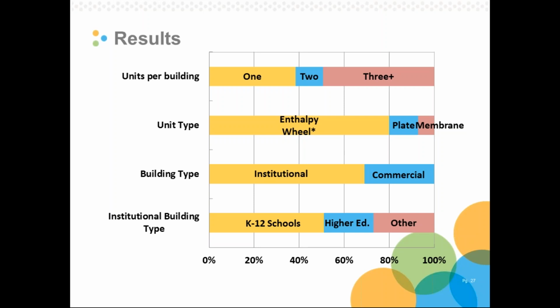As far as the type of energy recovery systems, total enthalpy wheels dominate energy recovery in commercial and institutional buildings in the state. 80% of units were total enthalpy wheels. To a lesser extent, we found plate heat exchangers that transfer temperature only, and to an even lesser extent, membrane heat exchangers transferring moisture and temperature. We know there are other kinds of energy recovery systems out there, heat pipes, runaround loops. We know specific examples of them, but in this data set, there were 0 occurrences, so evidently they're quite rare.